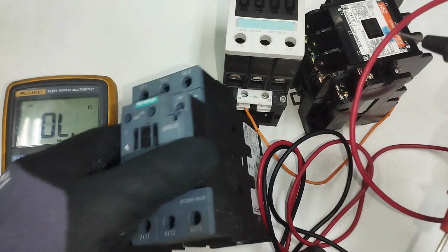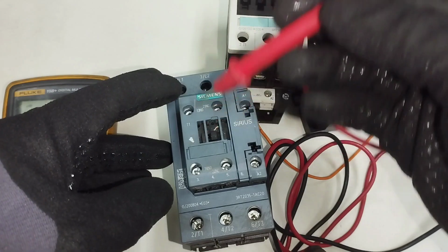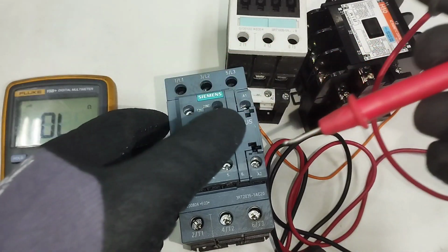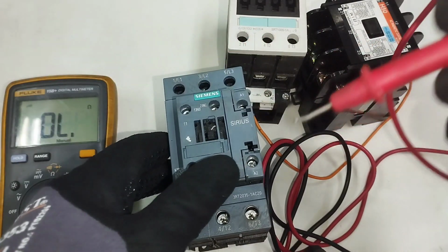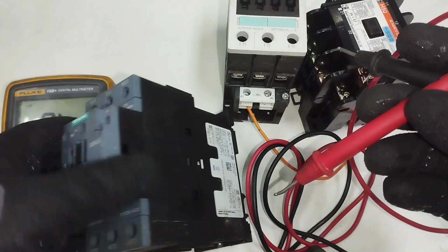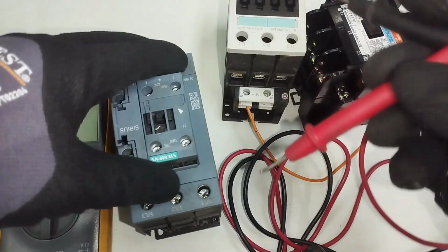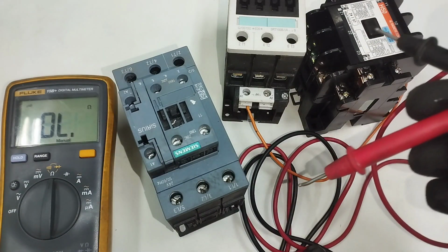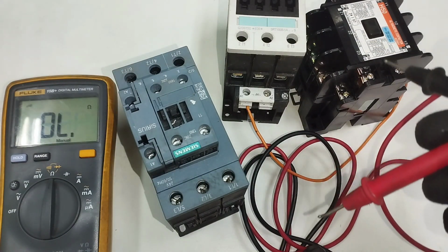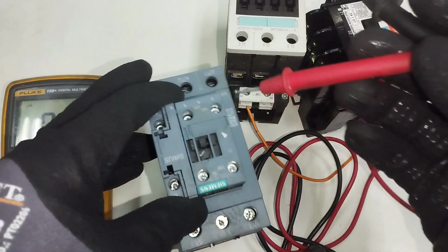So that's one of the reasons why your machine will not be running, or your machine will be running and all of a sudden, your machine will stop. So you have to confirm all these auxiliary contacts. Whenever normally closed becomes normally open, then your machine will stop running. So that is just it. Then the other parameters remain the same.